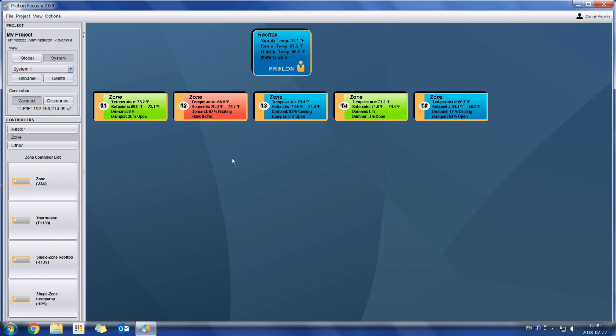Now we can notice that the icons have different colors. So if a zone is blue, it means it's calling for cooling. If the zone is red, it means it's calling for heat. And if the zone is green, it simply means that the zone is satisfied. Now these colors also apply to the rooftop as well. So if the rooftop is blue, it means it's actually cooling. If it's red, it is heating. And if it's green, it is simply ventilating. So let's say I want to configure one of these controllers. Well, I could simply double click on it.